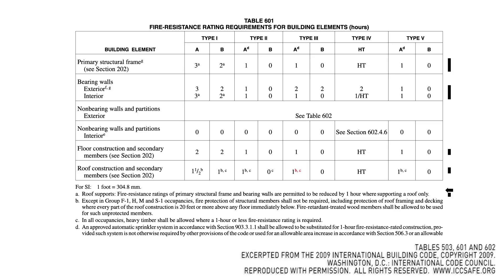There are variations on that depending on how much fire protection is provided on the elements of the building. To find out what the requirements are for the fire protections, you go to Table 601. Table 601 tells you the amount of fire resistance in a nomenclature of hours, and it categorizes it under type of construction.